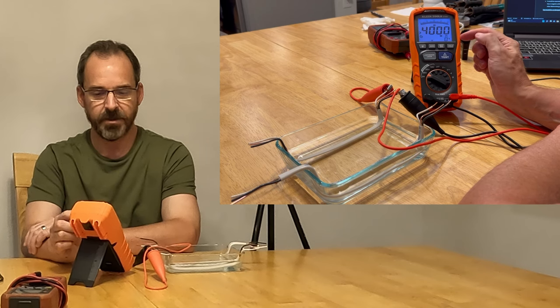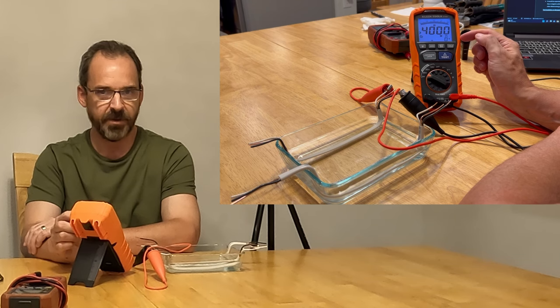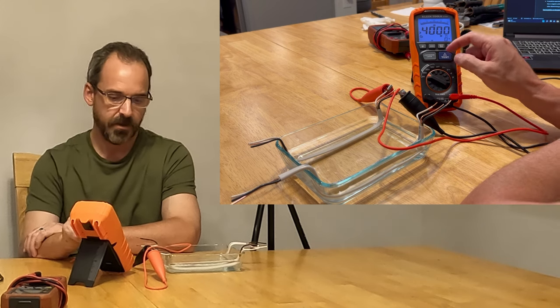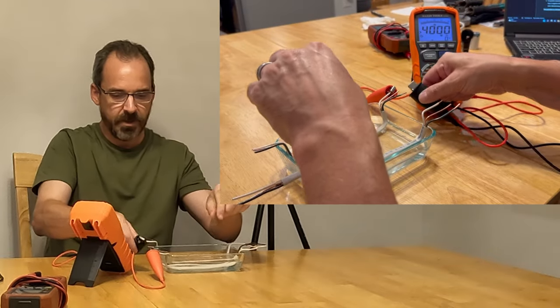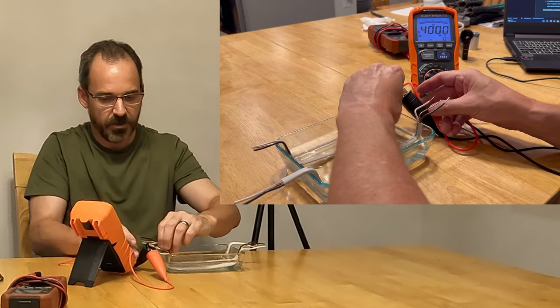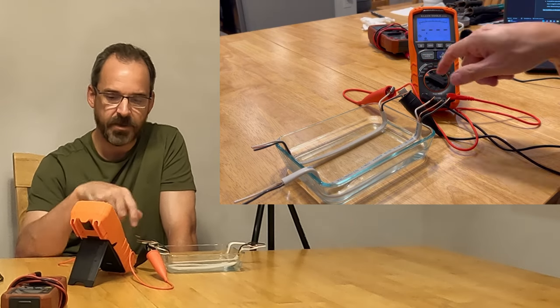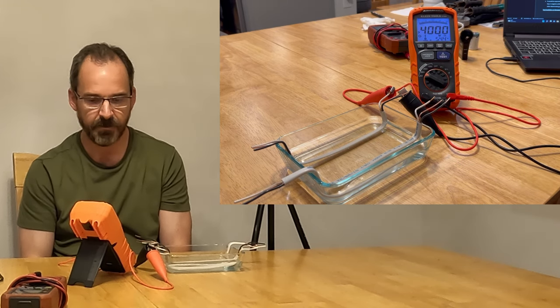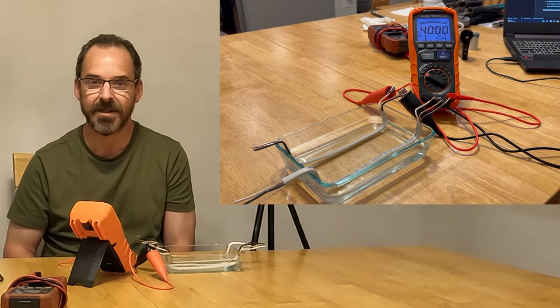So we can just release. And then the voltage returns to zero. So that voltage returning to zero, that's the capacitive voltage that's built up on the insulation during the test. You need that to return to zero before you do a new test. So let's test. So we know we're good between those conductors. So now let's test from white to ground. Make sure these are not touching each other. This one, I'll do the hands-free test. So to do that, I'm going to press continuous lock. Now we see the lock symbols there. I'll press test. And I'll give it some time. So this one's fine.